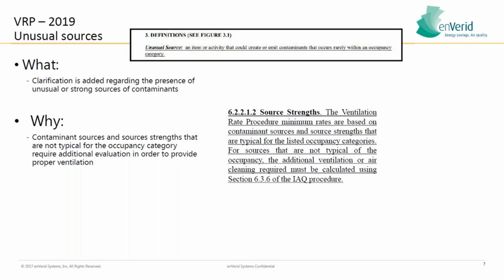And one thing that's interesting is that ASHRAE now recognizes that outside air is frequently polluted. You know, ASHRAE is a multinational organization now that it's worldwide. There are environments where ventilating according to the ventilation rate procedure is not actually ideal. So ASHRAE 2019 actually clarifies that if you are designing a building where contaminant sources and source strengths are not typical of the occupancy, so I'll give a couple of examples.